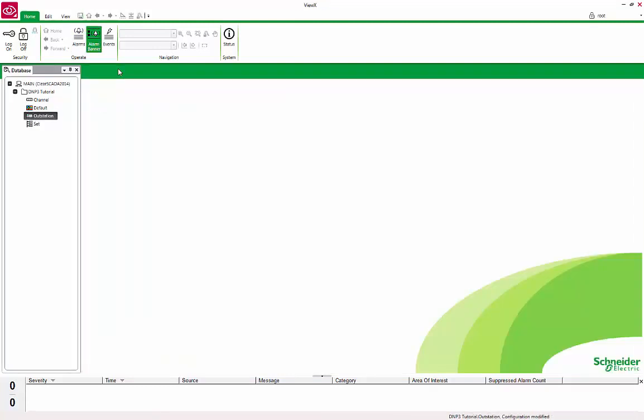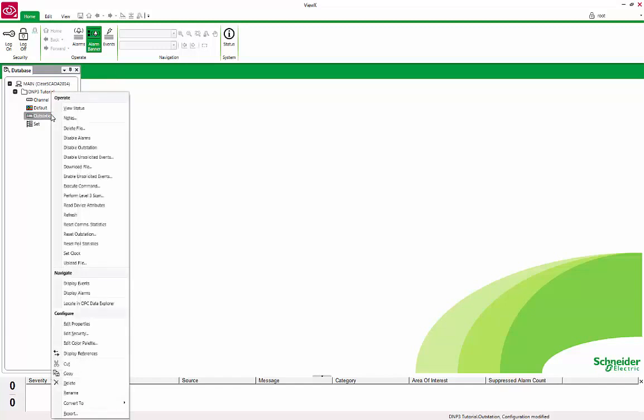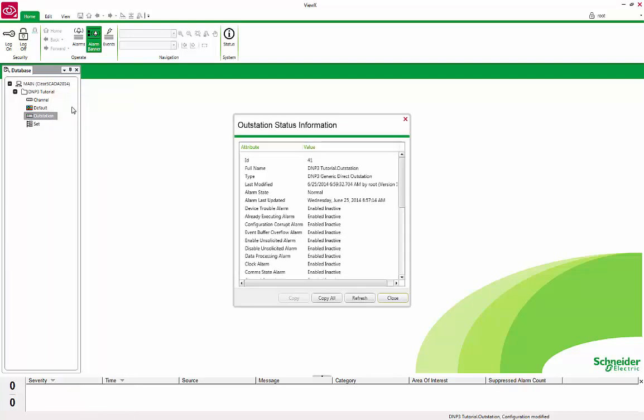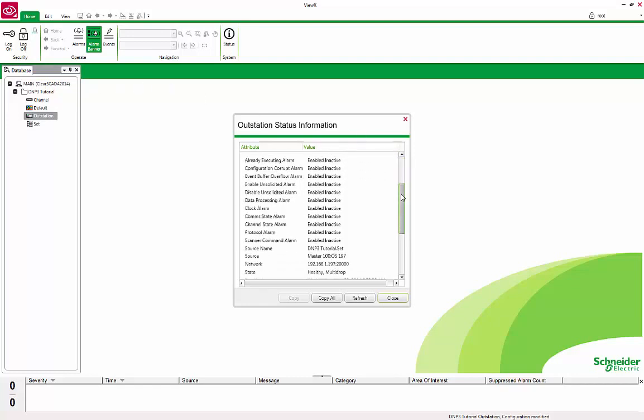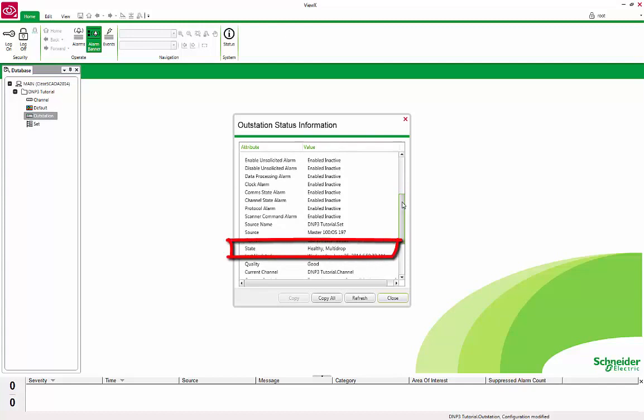Now that the configuration is complete, we can test to see if we are successfully talking with the device. In the Database Navigator, right-click on the OutStation object and select View Status. Scroll down and note whether the state field says Healthy Multi-Drop. If it does, then you are communicating to the device. If it does not, then check the settings for the device and confirm that they have been entered correctly in ClearSCADA.